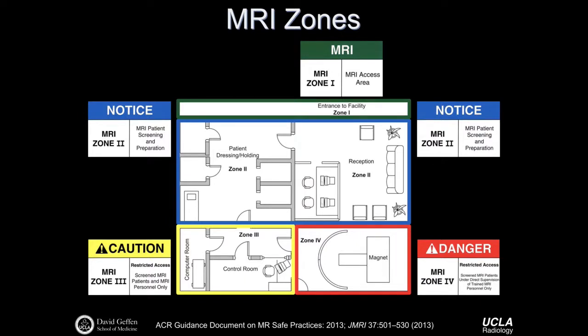The American College of Radiology defines different MRI zones. Zone 1 is general MRI access, the entrance to the facility. Zone 2 is where MRI patient screening and preparation occur, typically a waiting room or reception area. Zone 3 is restricted to screened MRI patients and MRI personnel only—the control area adjacent to the MR system. Zone 4 is for screened MR patients only, under direct supervision of trained MR personnel. Understanding these boundaries is critical to maintaining patient and personnel safety.